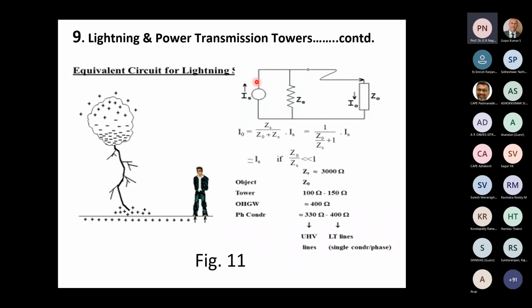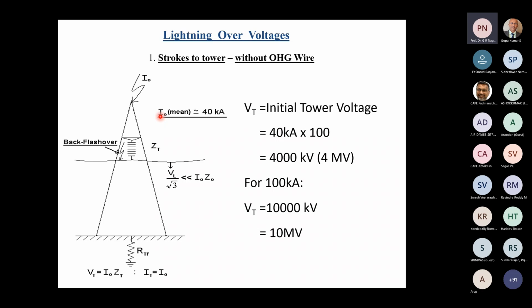So, the lightning stroke is represented by its current magnitude, for example 200 kA. It divides between its own surge impedance and the object surge impedance. That's how we calculate various parameters in the case of transmission lines. Now let's consider a simple case. Lightning has hit the tower top of a tower, no overhead ground wires anywhere, just a tower with the transmission line conductors strung by an insulator string. This may be a porcelain insulator string or a polymeric insulator string, whatever it is. It's insulated from the tower, otherwise this current will directly enter this phase conductor. Now assume 40 kiloamperes. It has a probability of 50% or more. Therefore, we'll consider 40 kiloamperes.